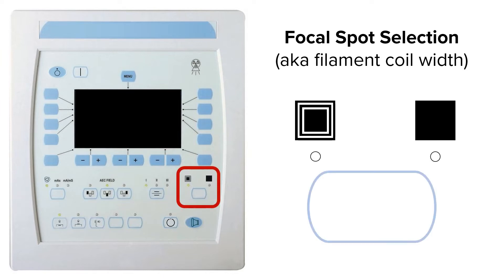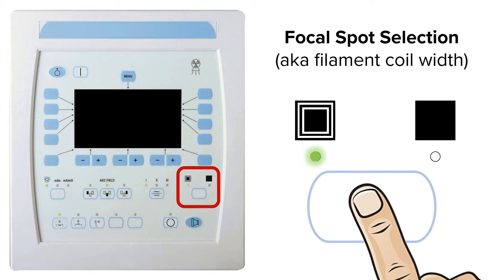As an x-ray tech, the only control you have over the size of the incident electron beam is by selecting the appropriate width of the filament coil. We do this by selecting either the small or large filament. You can select the small or large filament by selecting the small or large focal spot size on your control console.